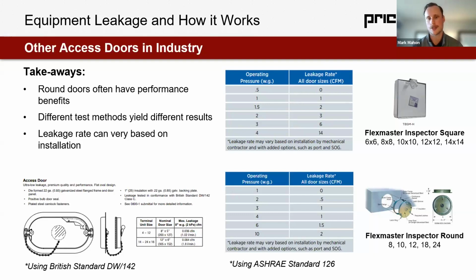So different FlexMaster doors have different leakage rates. We can see when we compare square access door, up to 14 CFM at 4 inches of pressure. Round, because of having no corners, the gasket seals a lot better. We see only 2 CFM at 10 inches of operating pressure. That is the door by itself. If the door is misinstalled, that leakage rate can increase. So round doors are a benefit, but proper install is a requirement.